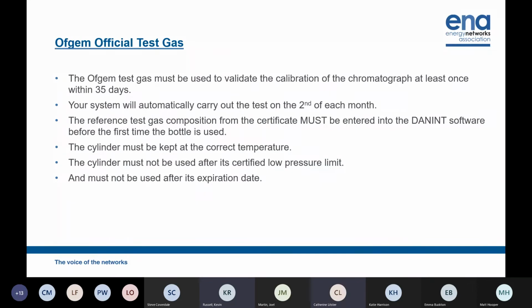Okay, so the official Ofgem test gas, this is much the same as the calibration gas, but this is used to validate the calibration of your CV determination device at least once within 35 days. You can do it more often, but it needs to happen once within 35 days. It should automatically carry this out. It should be set in your system to complete on the 2nd of each month at a time that doesn't interfere with the daily calibration run or the start and end of the gas day. It's the same as the calibration gas.